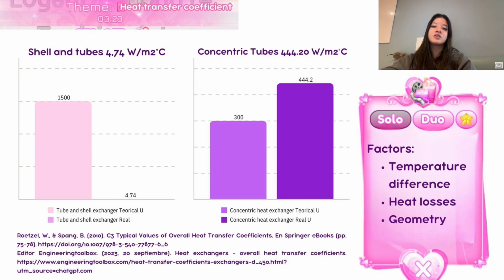The first one is the low temperature difference. The recirculation of the water during the operation caused the hot and cold inlet temperatures to be very similar, reducing the thermal driving force and the heat transfer efficiency, which depends on a significant temperature gradient, which was not achieved here, as you can see. The second aspect is the constant and significant leakage. A large leak led to heat losses and reduced the fluid volume within the exchanger, significantly decreasing the capacity to transfer heat. This also disrupts the flow patterns, reducing the efficiency of the cross-flow or the counterflow configuration. So we can conclude for this exchanger that the operational issues explain the extremely low U-real, indicating that the exchanger is underperforming and requires adjustment in operation and possibly design.